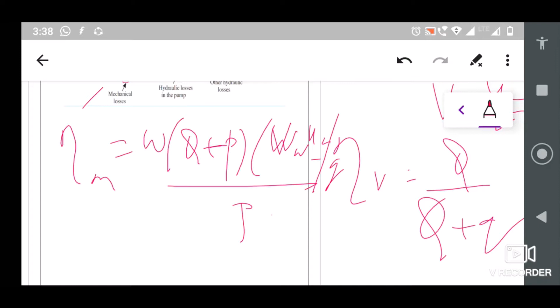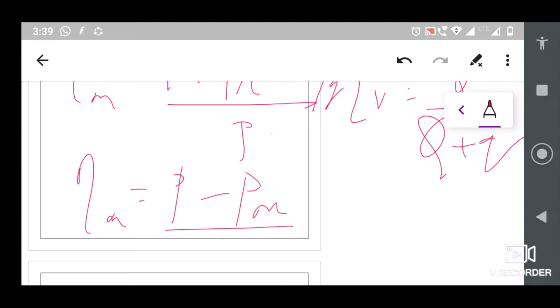Next you have the mechanical efficiency. Mechanical efficiency is the ratio of the power delivered by the impeller to the liquid to the power input to the pump shaft. If you write it over here, it would be W into (Q plus q) into V_w2 into U2 by g, by P. From this, with a simple substitution, you would get the mechanical efficiency as P minus P_m by P. This would be your actual mechanical efficiency.